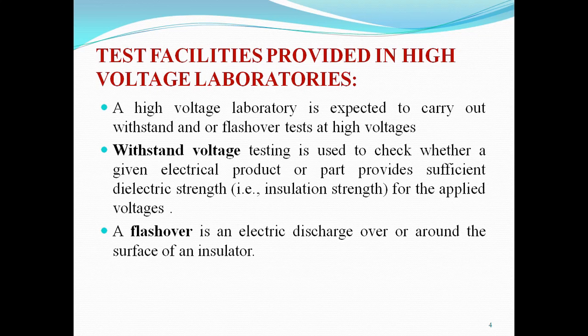First of all, what is the meaning of withstand voltage? Withstand voltage testing is used to check whether a given electrical product or part provides sufficient dielectric strength, meaning insulation strength, for the applied voltages. And a flashover is an electric discharge over or around the surface of an insulator.